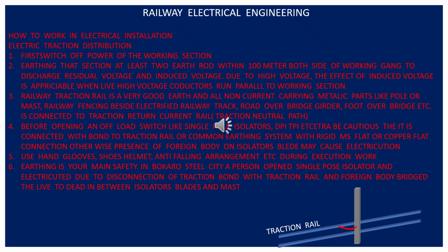Figure shows an electric mast, a traction mast, just beside the railway track. As per safety, it is non-current carrying, because all the OHE materials are above the mast, not on the mast. We are fixing the cantilever, but with insulators, and for the isolator it is also post insulators. So the mast is dead, but above the insulators, these are all live. Everything connected with the insulator is live at 25 kV or some higher voltages in the substation. So it is our safety that the insulator is protecting us, but it is not enough.